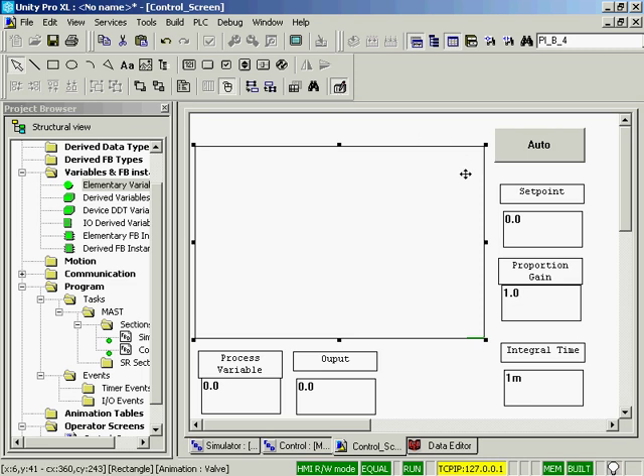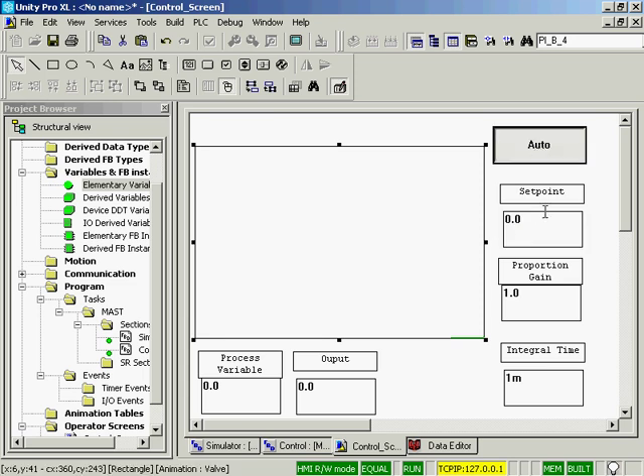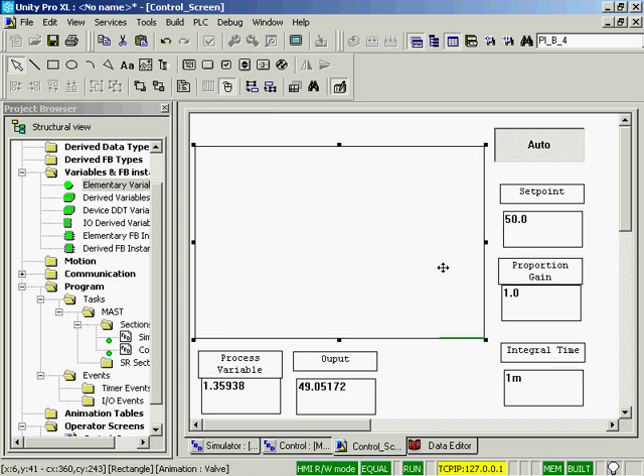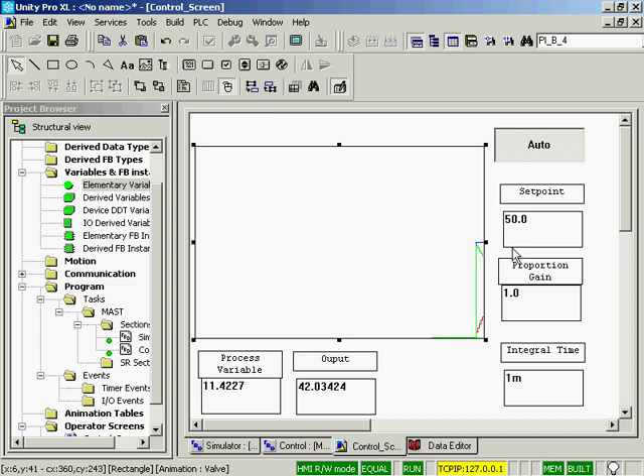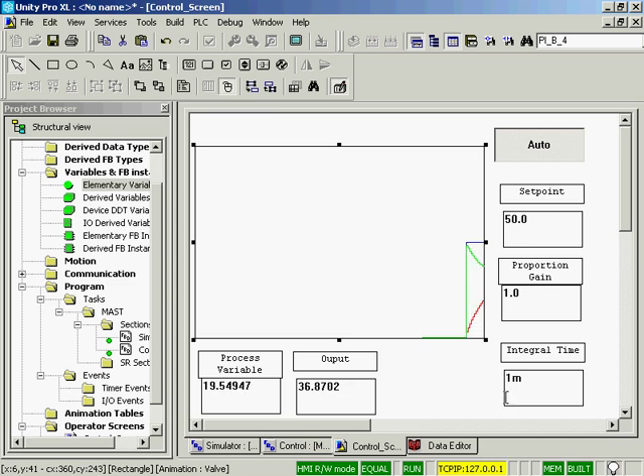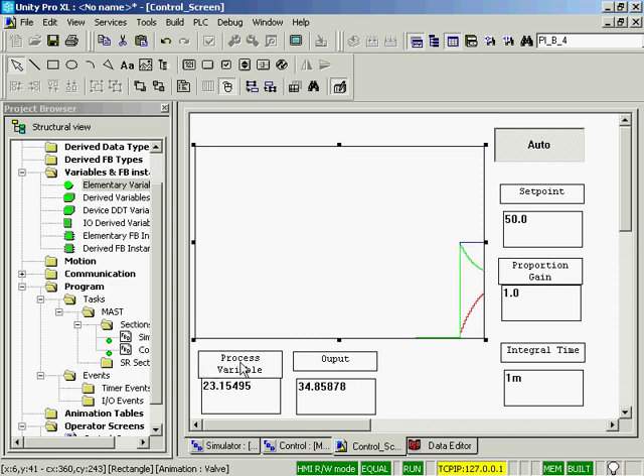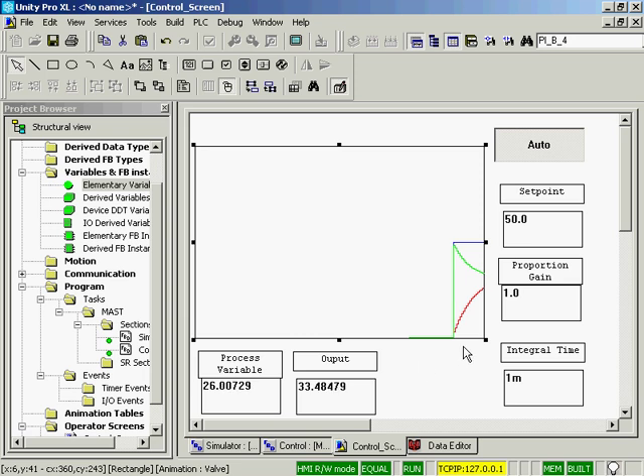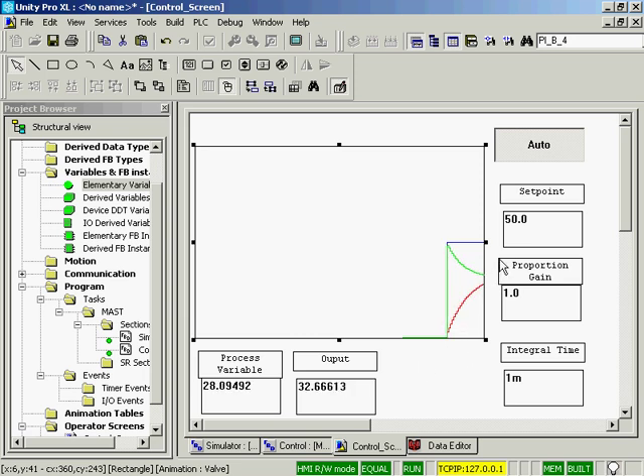Currently we have no setpoint. We have a proportional gain at one. We have an integral time of one minute. I'm going to put it in auto first. I'm going to set a setpoint of 50 degrees. And we see our blue setpoint go up. The valve is the green. So it went up to 50 and it starts slowing down. And you'll see that the process variable is slowly working its way up to 50 on the setpoint.